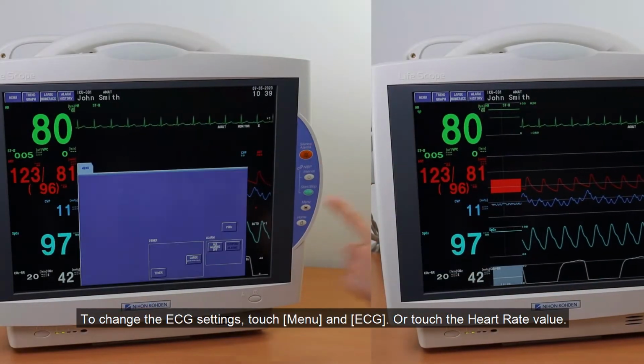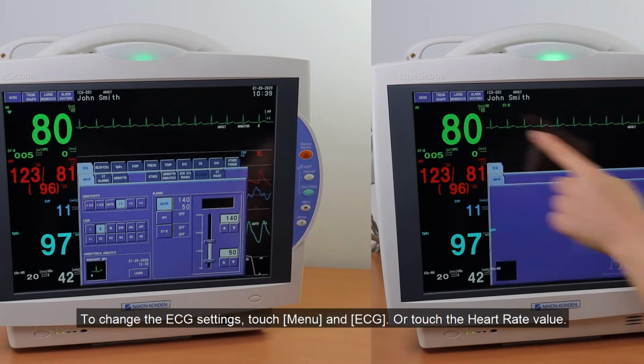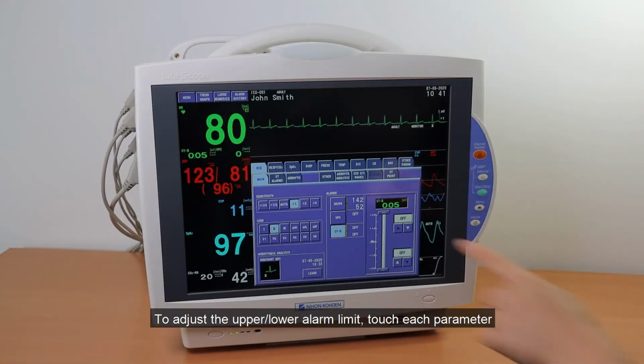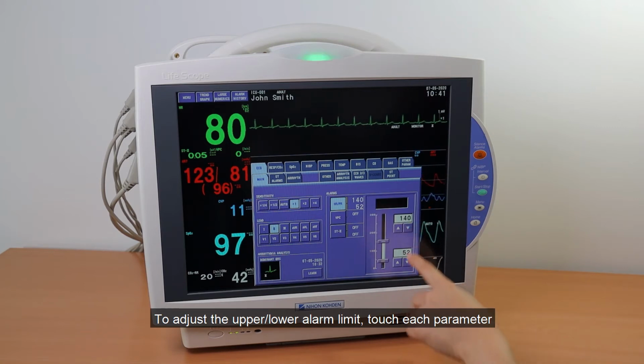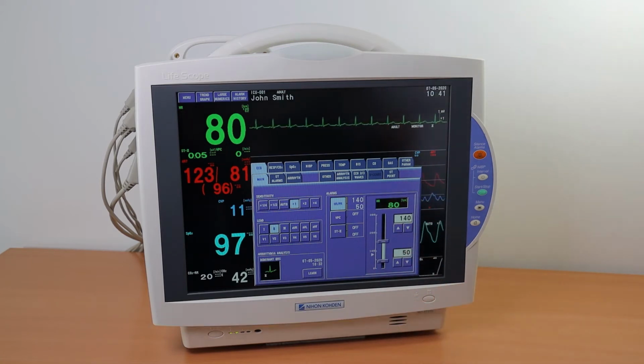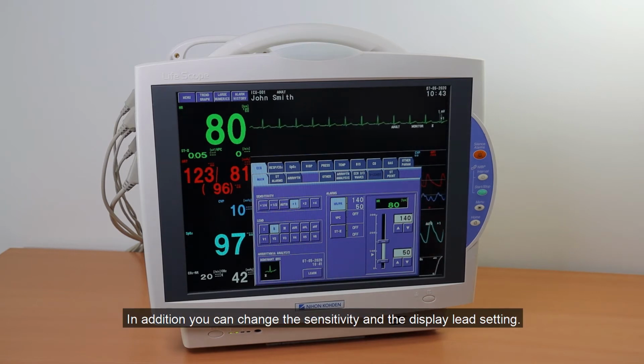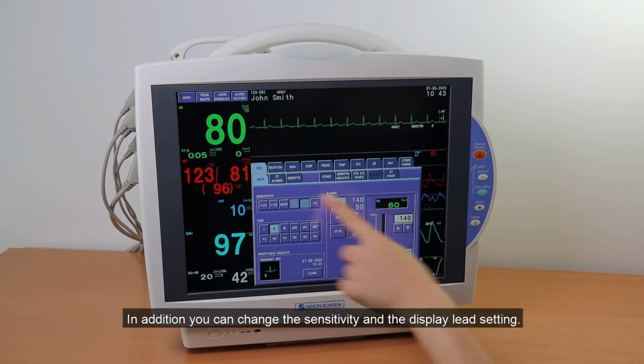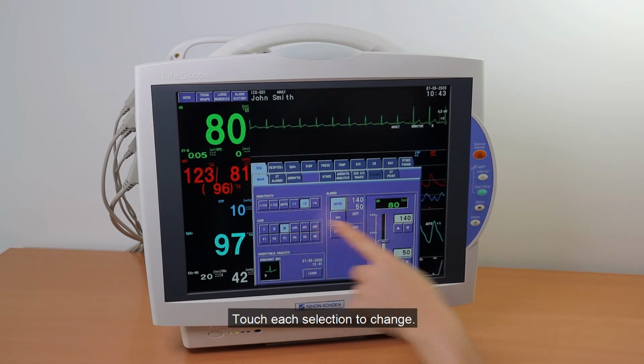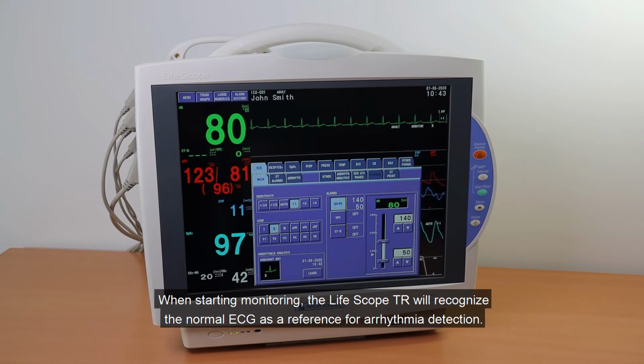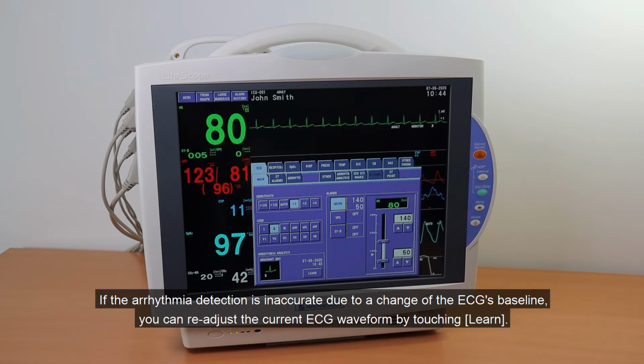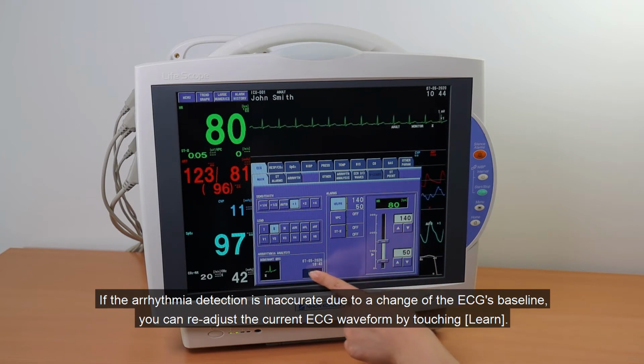To change the ECG settings, touch Menu and ECG, or touch the heart rate value. To adjust the upper-lower alarm limits, touch each parameter. In addition, you can change the sensitivity and the display lead setting. Touch each selection to change. When starting monitoring, the Life Scope TR will recognize the normal ECG as a reference for arrhythmia detection. If the arrhythmia detection is inaccurate due to a change of the ECG's baseline, you can readjust the current ECG waveform by touching Learn.